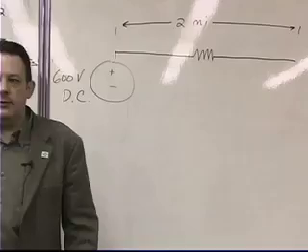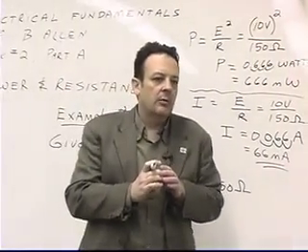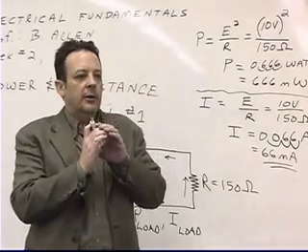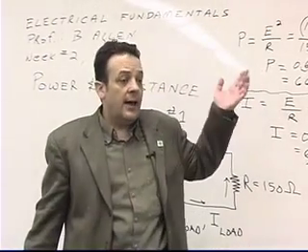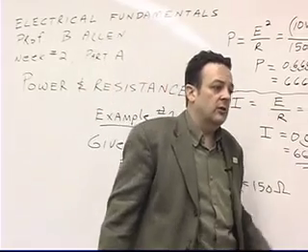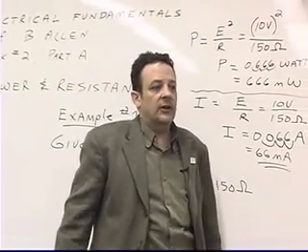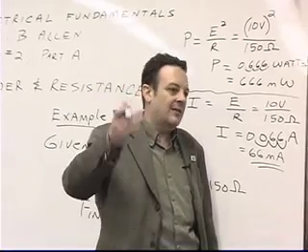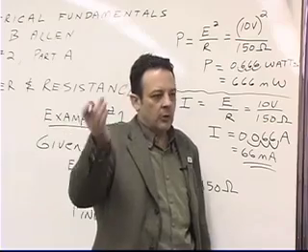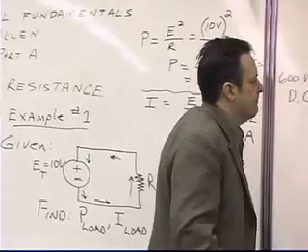And if we got 2 miles of cable, even if it's fairly large cable, say it's double aught cable or single aught cable, it's pretty big around, okay? It's going to have some resistance. And the manufacturer of the cable is going to usually designate the resistance in ohms per 10 feet or ohms per 100 feet or ohms per so many feet, okay?